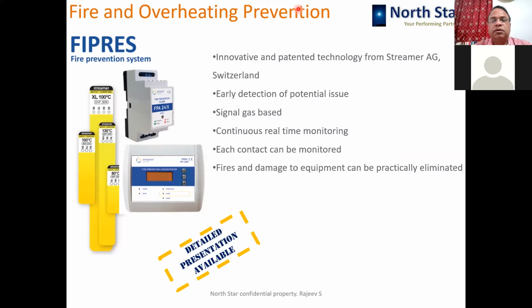It is based on gas technology, where a gas is released from these kind of stickers which are put on any contacts. So as far as the transformer is concerned, these can be put in your cable boxes near the cables, in your control panels, your LV bushings where you feel that there is heating happening, especially solar transformers where a lot of issues are coming because of heat in the LV bushings or input side. So there these systems can be put, and it can give you a well-before alarm about the incipient danger, and it can prevent big failures and interruption in the services.